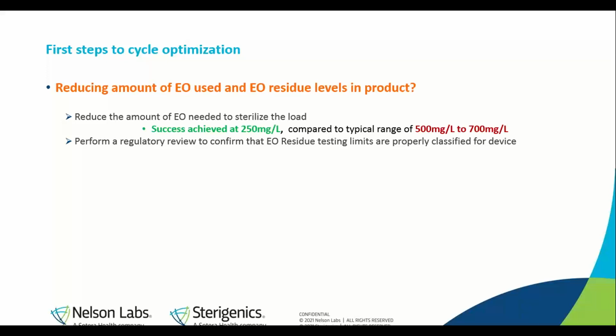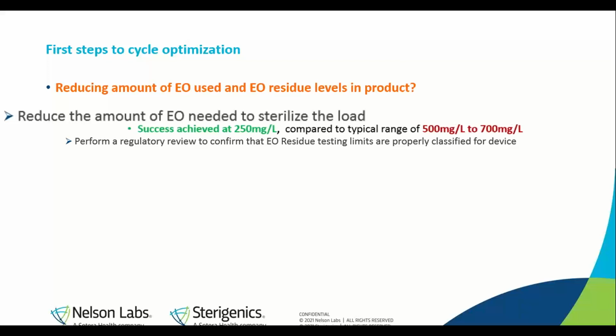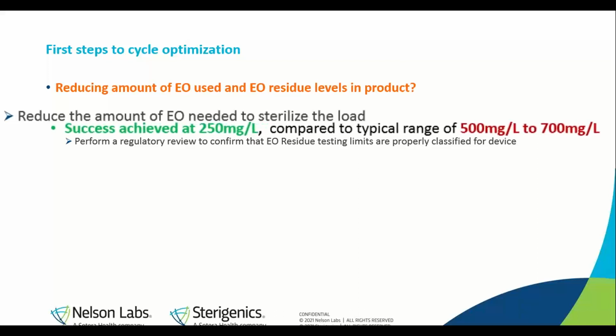Second bullet point is reducing the amount of EO used and EO residue levels in the product. This is probably the most popular target that we've seen in the industry over the last 6 to 9 months. Obviously, to accomplish this, I would be focusing primarily on reducing the amount of EO needed to sterilize the load. Traditionally, we've seen gas concentrations for the cycle be somewhere in the range of 500 milligrams per liter up to 700. But today, in the industry, we've seen success even at the lower gas concentrations of 250 milligrams per liter. Great improvement and a significant reduction in EO utilization.